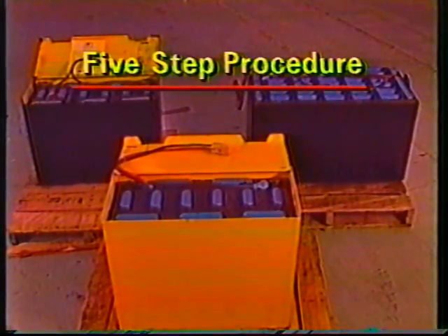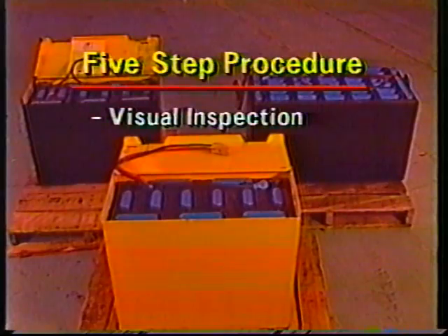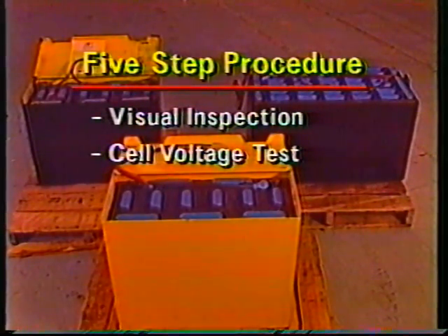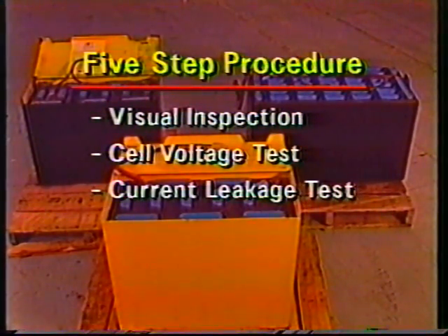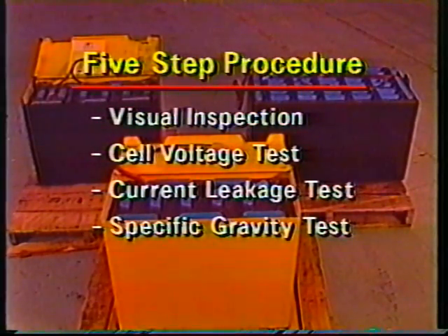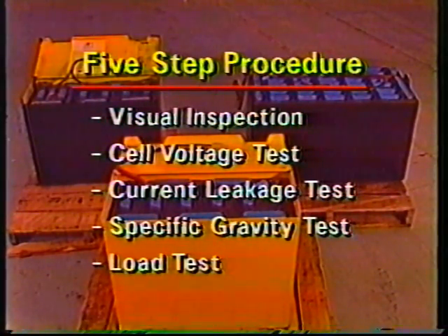After performing this 5-step procedure, the visual inspection, the cell voltage test, the current leakage test, the specific gravity test, and the battery load test, run the truck. If it still isn't running properly, the battery isn't causing the problem. So you can begin to troubleshoot other components.